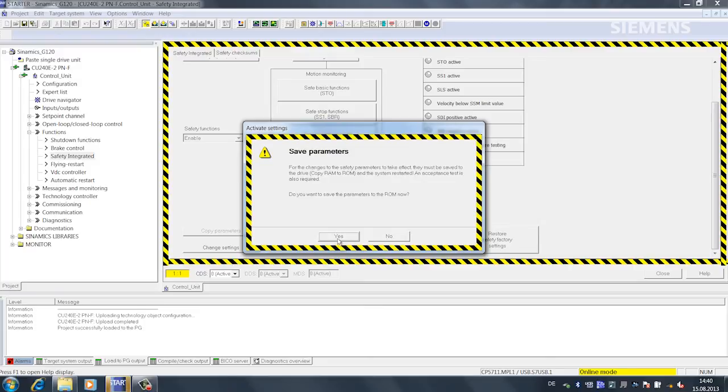Now we are asked whether we want to copy RAM to ROM. This is always necessary since the drive must be turned off after we changed the safety functions. With RAM to ROM, the data is now saved.